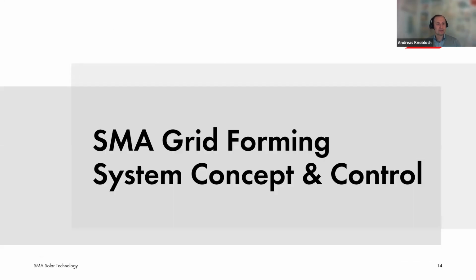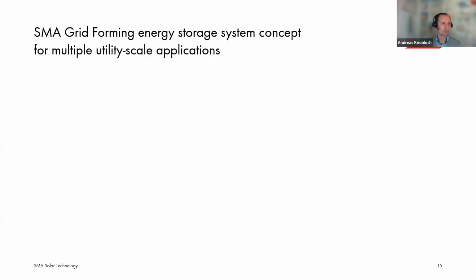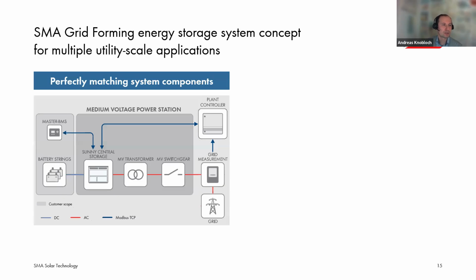So looking at the SMA grid forming system concept and control, how does it look like? How is it built up? And I will explain it on the grid forming solution concept for our battery energy storage systems at utility scale. So on one side, we have perfectly matching system components where the inverter acts as a voltage source and the transformer acts as an impedance, of course, with the impedances within the inverter.